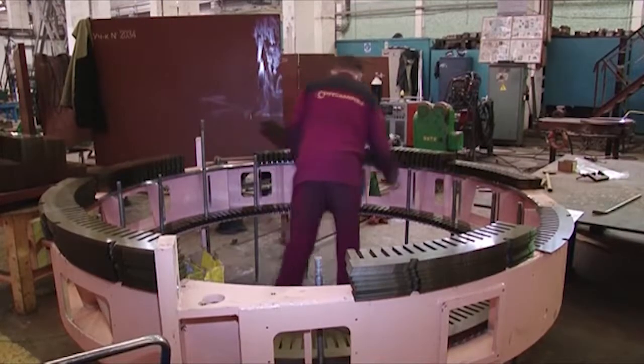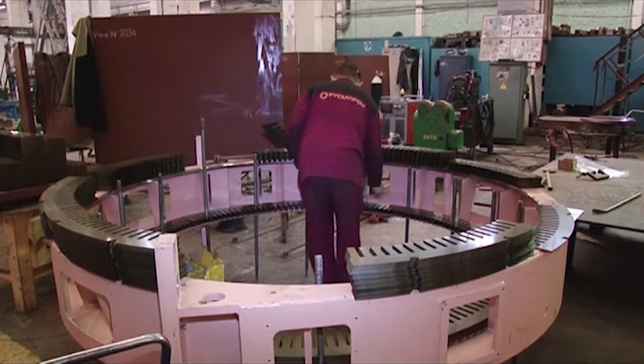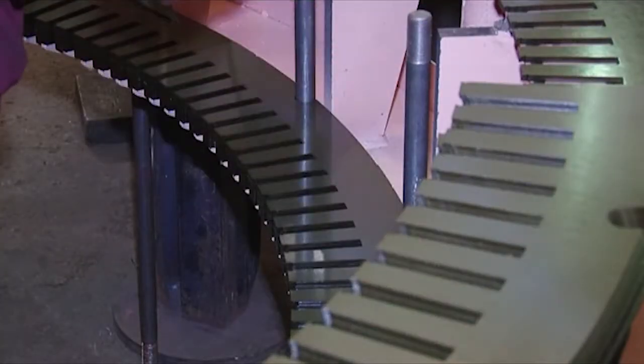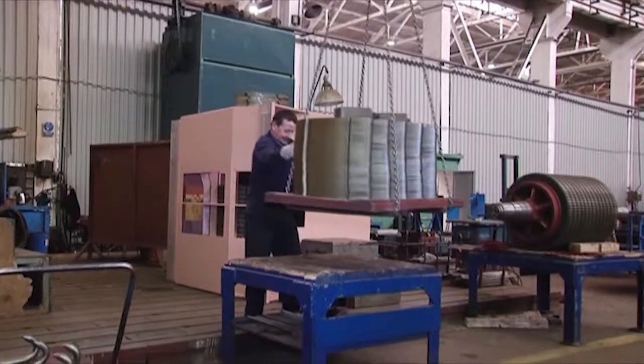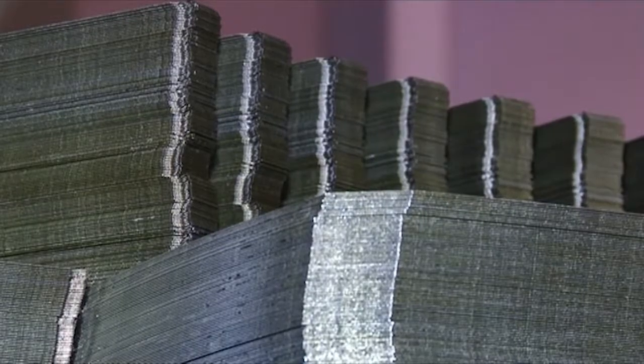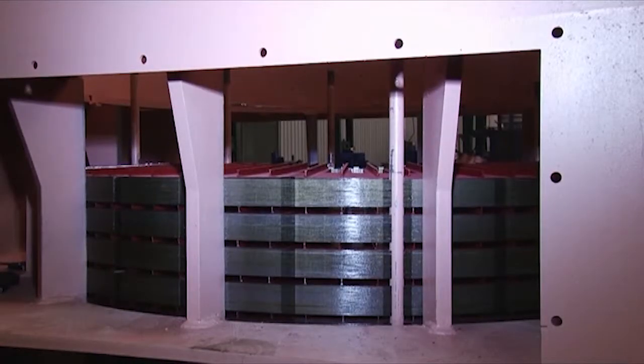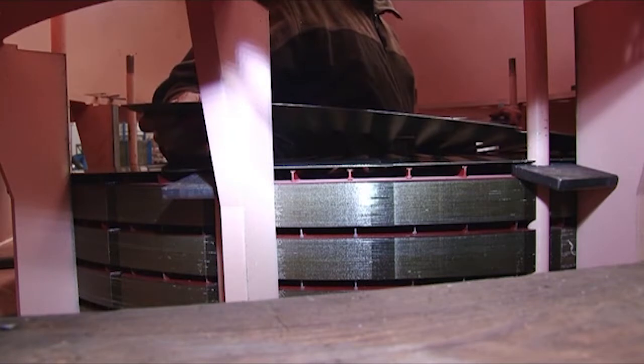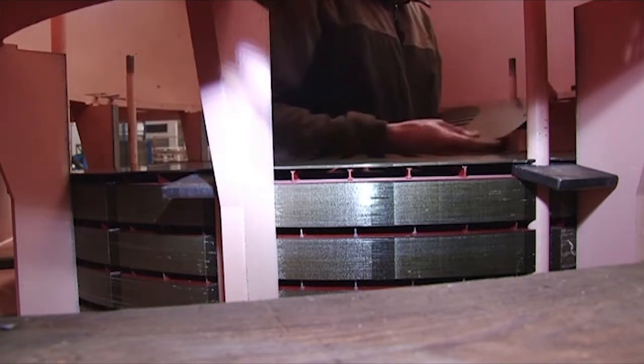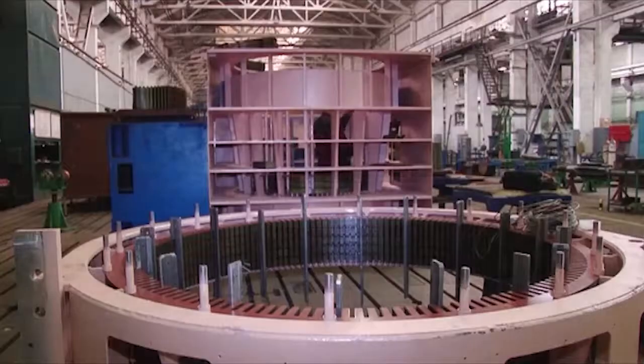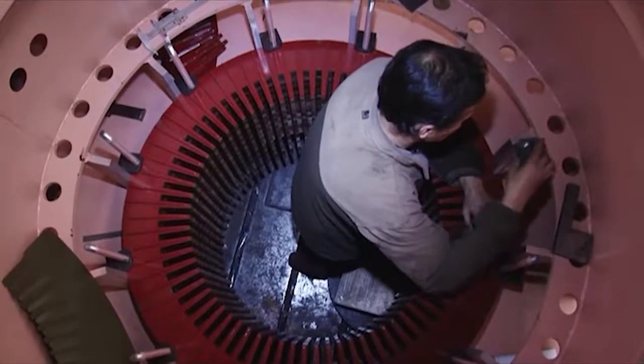The magnetic core is made along the stator body circumference after completion of the stator body manufacture. This core is another hollow cylinder made of a stack of 0.5 mm thick electric steel laminations. The magnetic core is assembled from separate segments since the stator diameter sometimes amounts to several meters. Packing washers are installed between certain numbers of the segments.